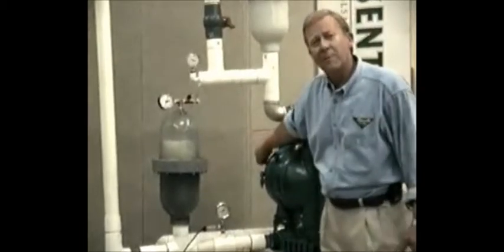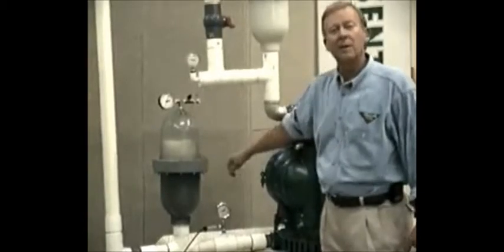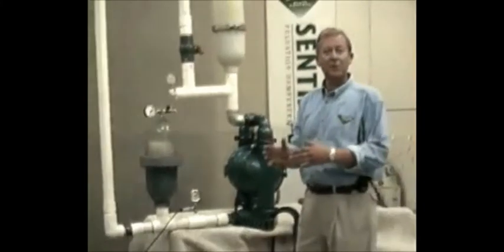But the other side of the pump is opening its inlet valve ball to accept liquid. It's a low pressure area. The spike rushes over there, slams into the diaphragm and distorts it.